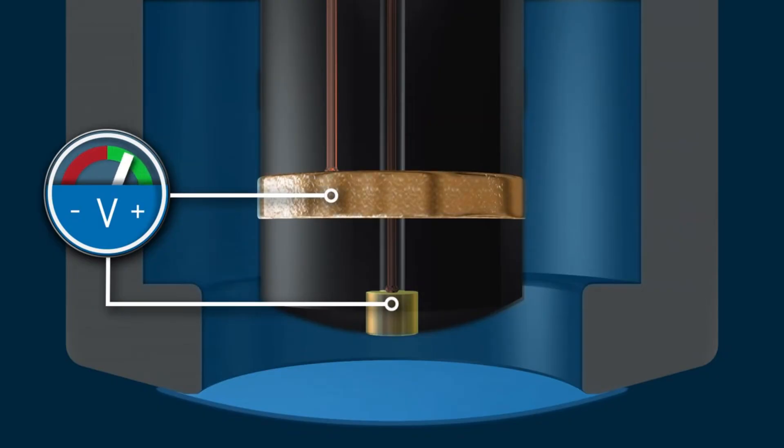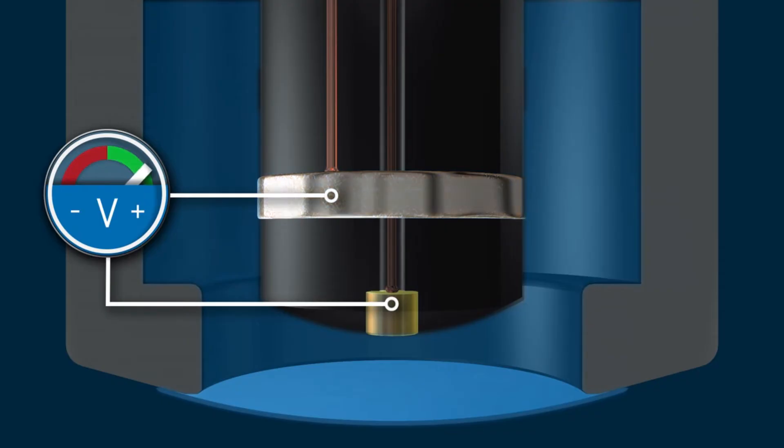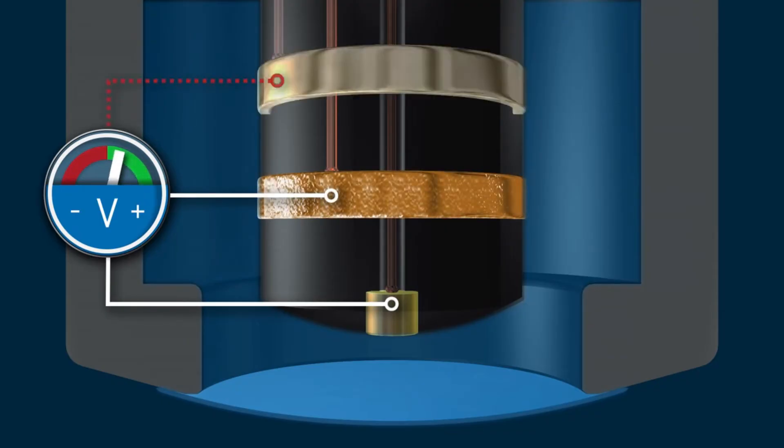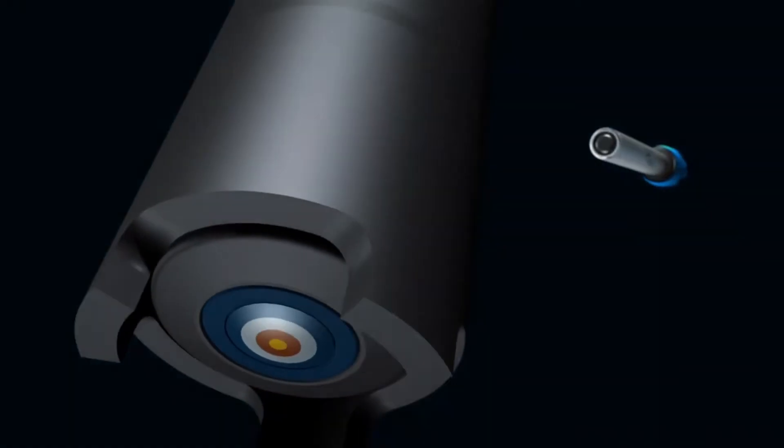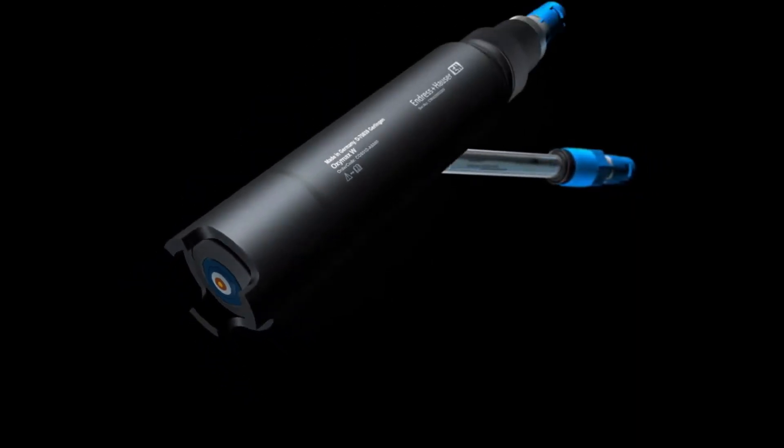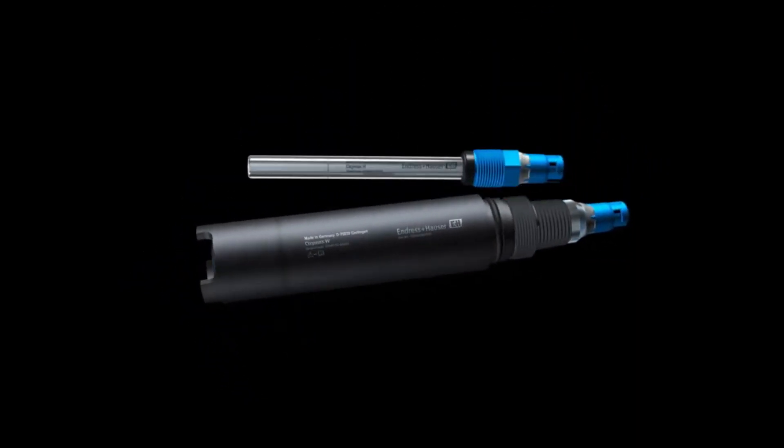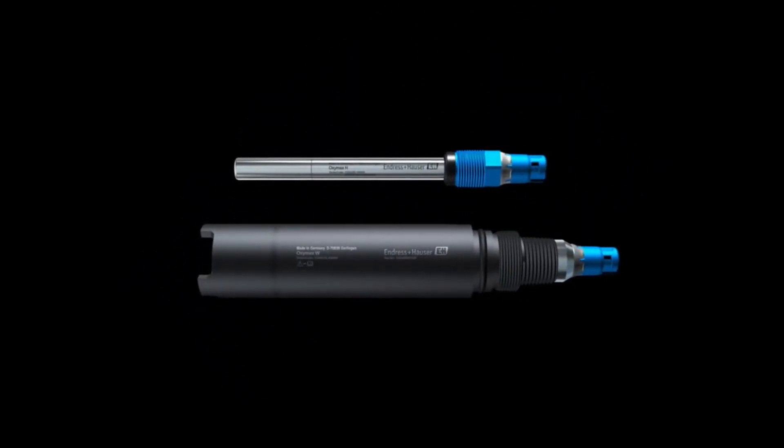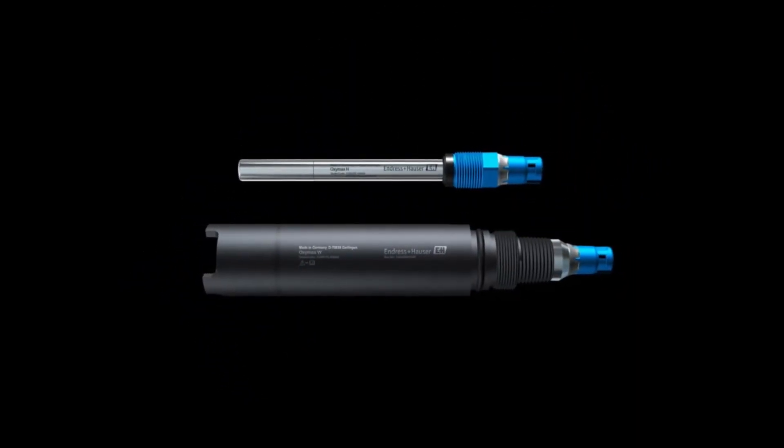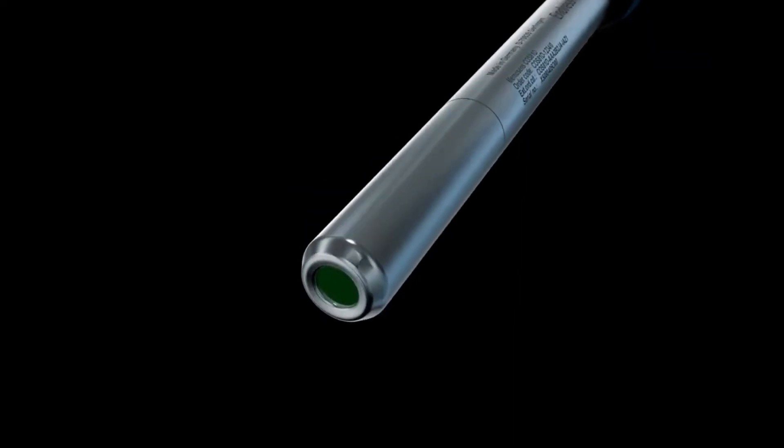There is a polypropylene membrane which is O2 permeable preventing bacteria, proteins and sediment from traversing it. These interfere with the measurement and interpretation of the oxygen values, especially the bacteria which consumes excess O2 and thus skews the values. The determinant of current flow is by use of the polarogram.